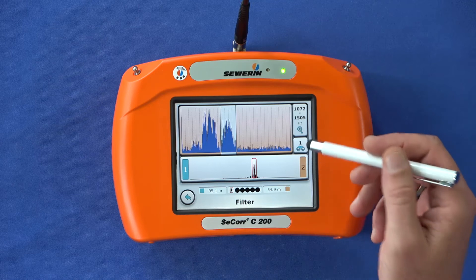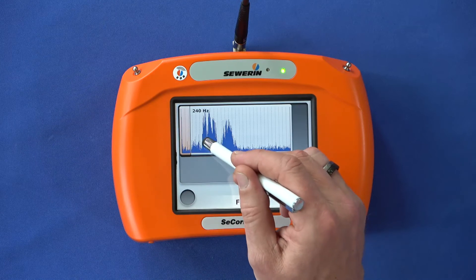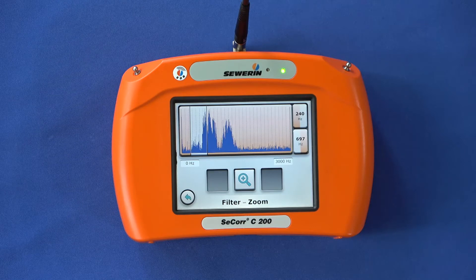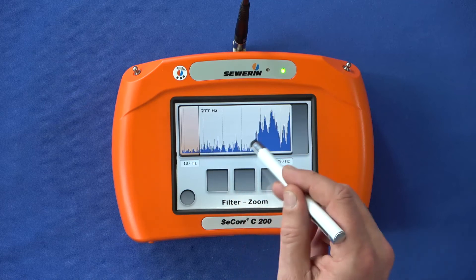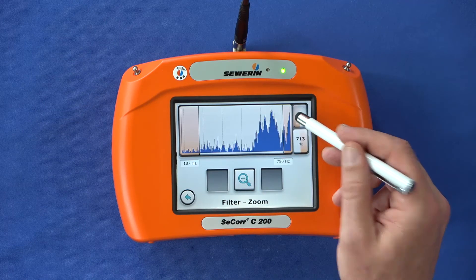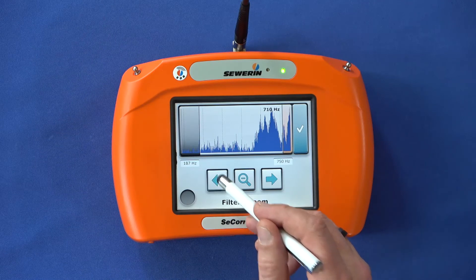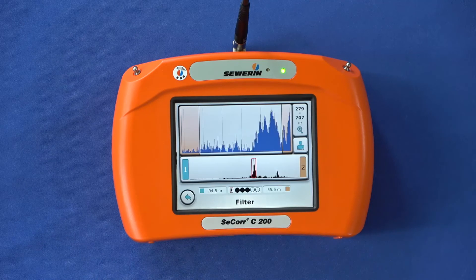If you want to set a filter manually you have two options. You can roughly set the filter by tapping the curve of the filter base, or fine tune it down to 1 Hz with the filter limits button. This takes you to the filter zoom dialog, where you have the option of zooming the filter base to the selected section. This enables you to recognize optimization potential even better. In this dialog too you can select the filter limits by tapping directly in the filter base, or set precisely using the two buttons upper and lower filter limit. Exit the filter zoom dialog with the back button — your settings are applied.